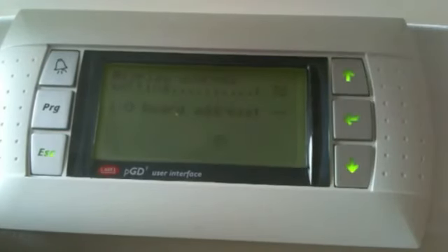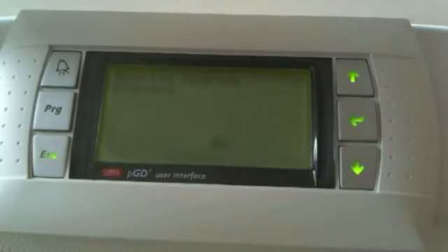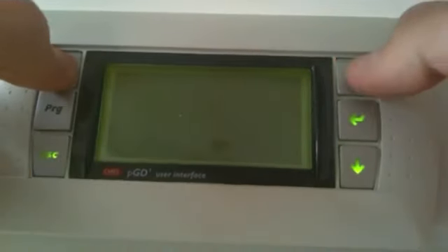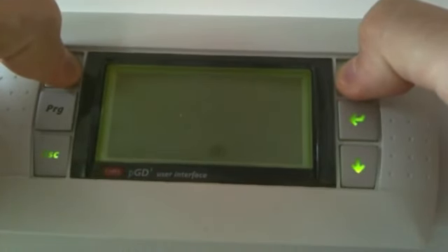Once the address is set to 00 — just for a temporary period of time — we have to set the controller's address to 01. To do this, we have to power off and then back on the controller, and during its boot-up procedure press the alarm bell and the UP key together simultaneously for some time.